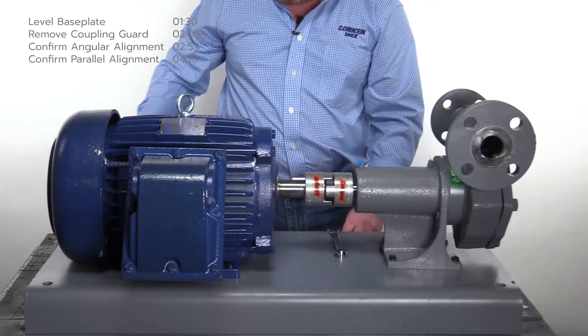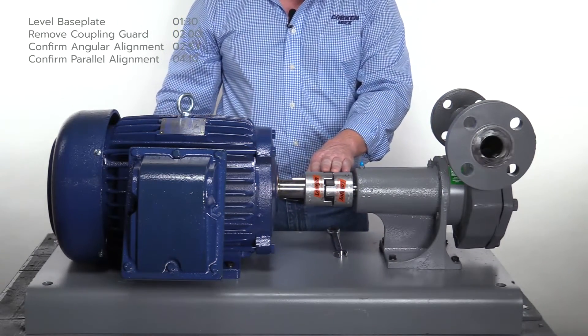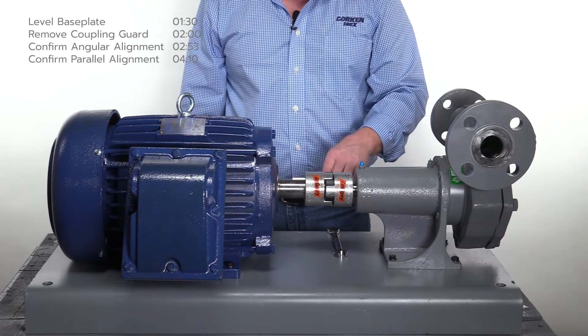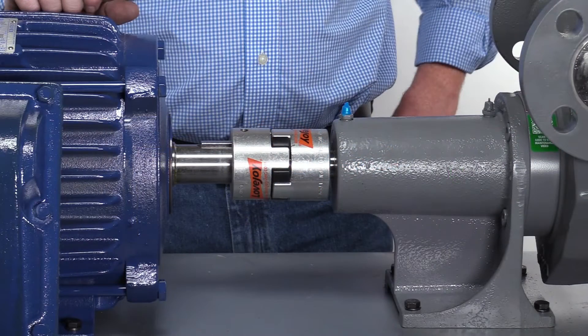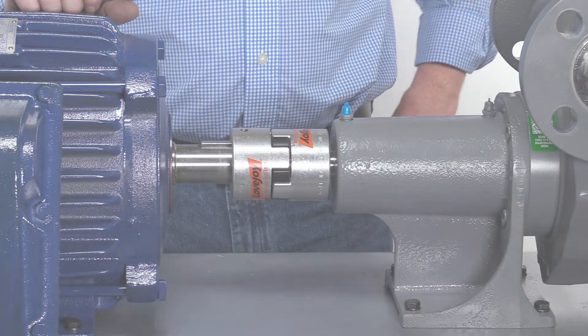Many of Corken's pumps utilize a flexible coupling that transmits power from the motor to the pump. Between each half of the coupling is a rubber spider gear that allows for a small amount of misalignment. However, measurements must remain within tolerance. The coupling also provides vibration dampening and acts as a fuse in case of torque overloads.